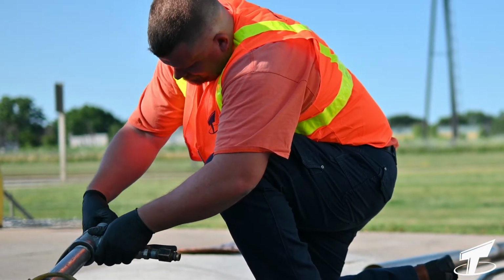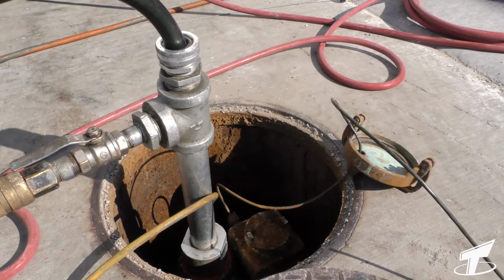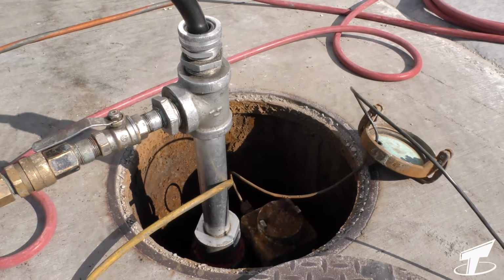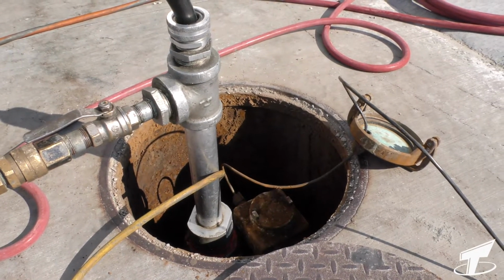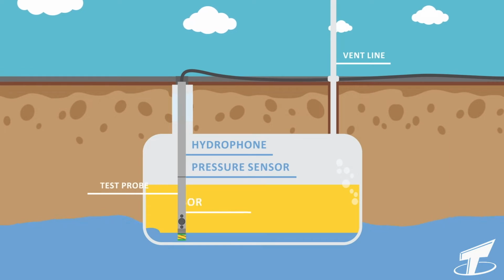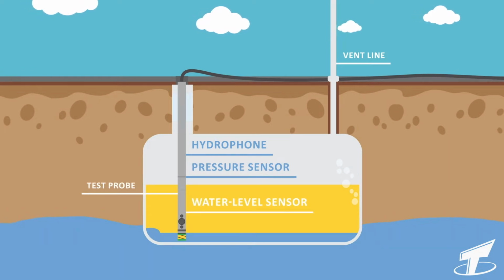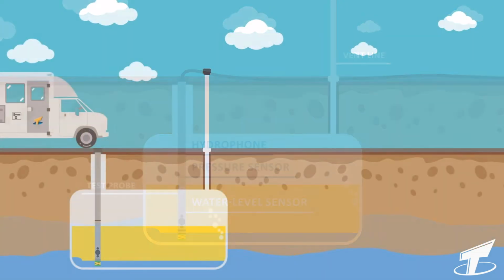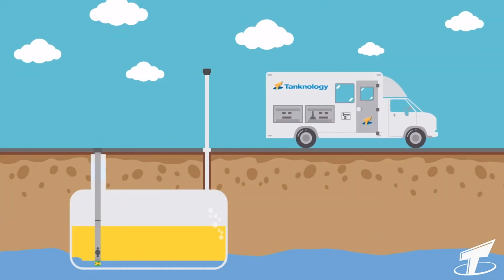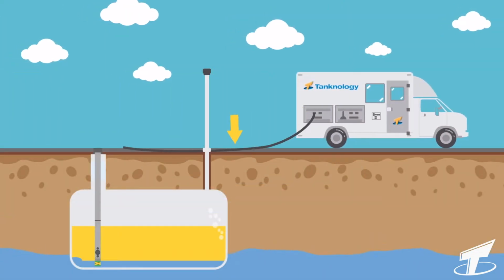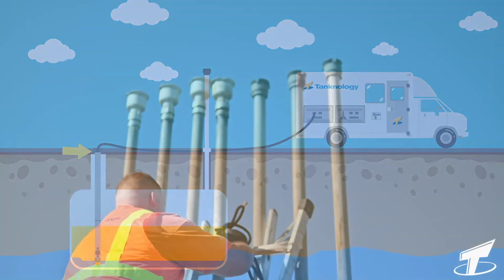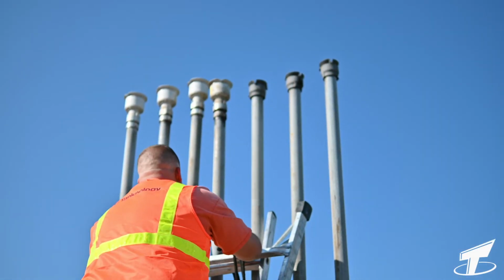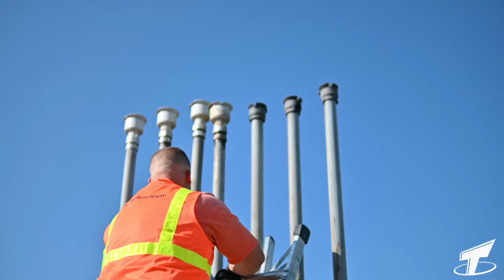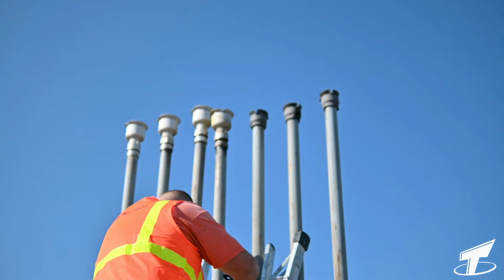An intrinsically safe electronic probe is lowered through the fill pipe into the tank, coming to rest just on the tank bottom. The probe contains a hydrophone, a pressure sensor, and a water level sensor. Signals from the probe travel up a cable to a specialized computer in the VacuTect mobile test unit. After the probe is lowered into the tank, all openings to the tank are temporarily sealed, making the system airtight.